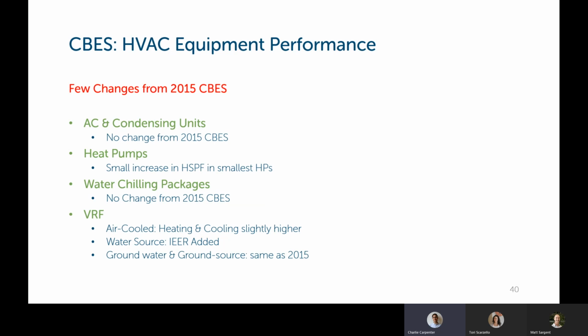For the performance of the individual pieces of equipment, I don't have them here, but there's a bunch of tables for all the different types of equipment that you could have in a building. There are actually very few changes from the 2015 commercial energy code. That's mostly the same. So air conditioners and condensing units, there were no changes. Heat pumps, there's a small increase in the seasonal heating performance in the smallest capacity heat pumps. Water chilling packages, there's no change. And for VRF systems, the air-cooled VRF has slightly higher heating and cooling efficiencies, water source VRFs, a seasonal IEER efficiency has been added, and ground and water source VRFs are the same efficiencies as 2015.